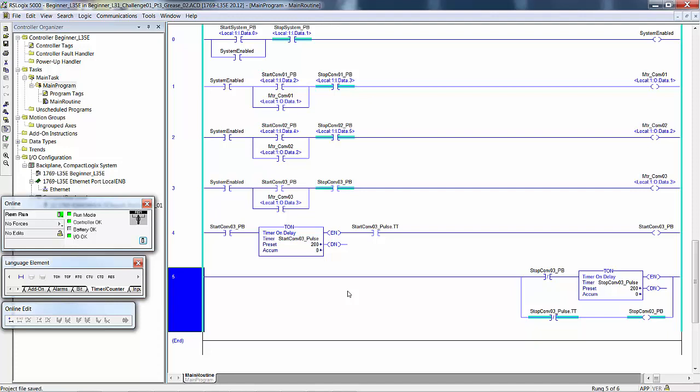Whenever you go out to a machine on the plant floor or at the customer site, you always immediately upload what's in the machine and save it with a name that you recognize with today's date. Usually I'll call it green machine as is, and then I put in the date, and I might even put in the time, or I just put AM to show that I saved it in the morning when I got there.